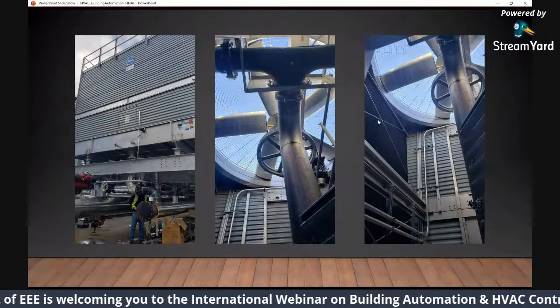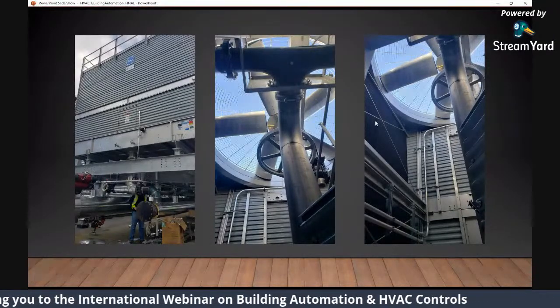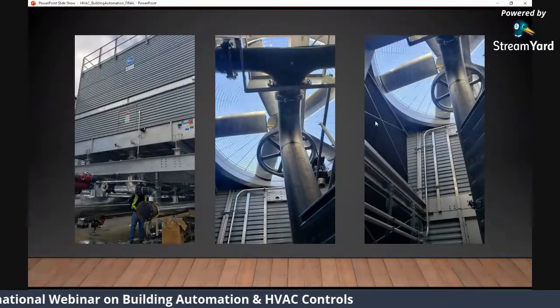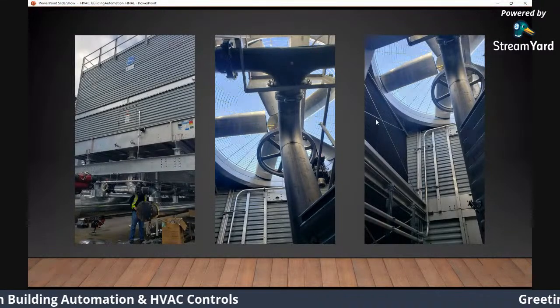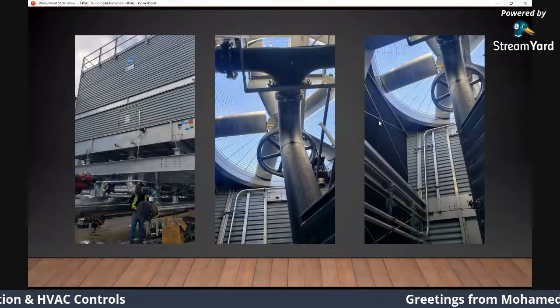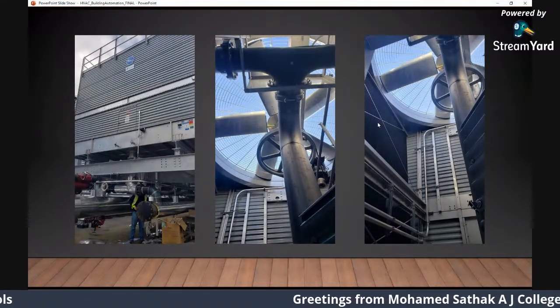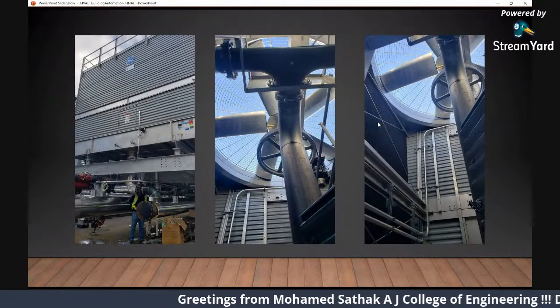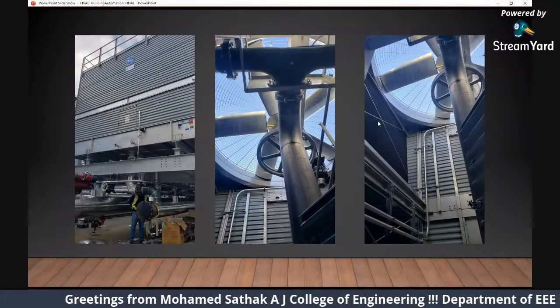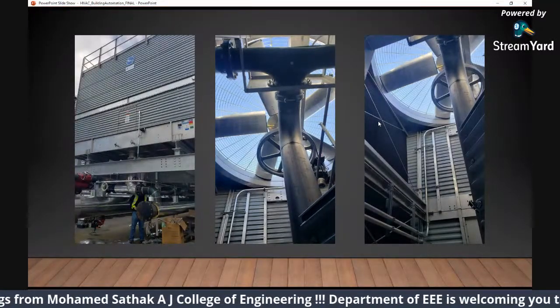All right. Just think of it as a concept similar to your tea master. That's how I explain it in simple terms. So there's a fan above the tea master. If you pour the water between two cups, it gets cool. That's the evaporative cooling method. And if you just blow air into the cup, it's called the heat rejection method, which is the air cooled chiller. So that's the difference between air cooled and water cooled.